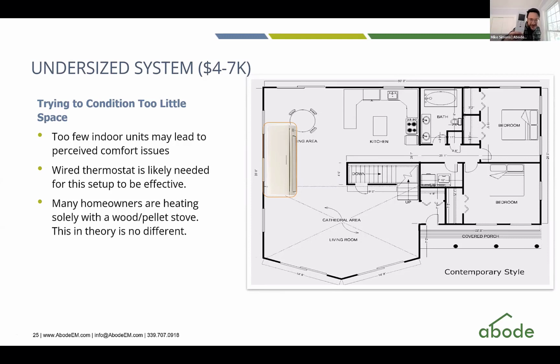If you're just controlling the unit with, say, a handheld remote, all this does is tell the unit to run an algorithm inside of itself until it's 70 degrees. But that algorithm inside of the unit doesn't know that, say, this bedroom is 65 degrees. So it just helps guarantee that the space you're trying to condition actually gets to that temperature before the unit tries to short cycle.